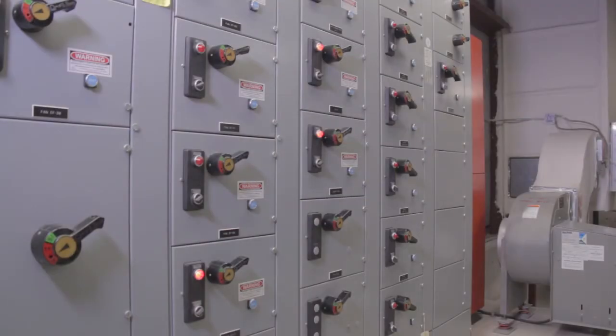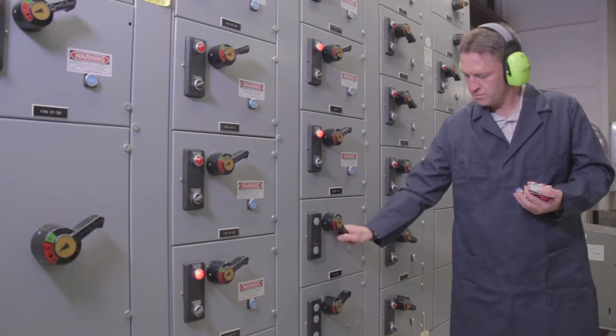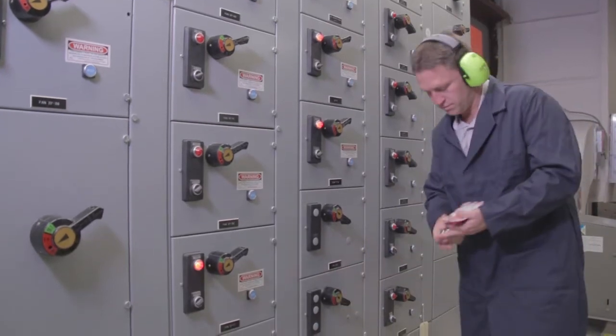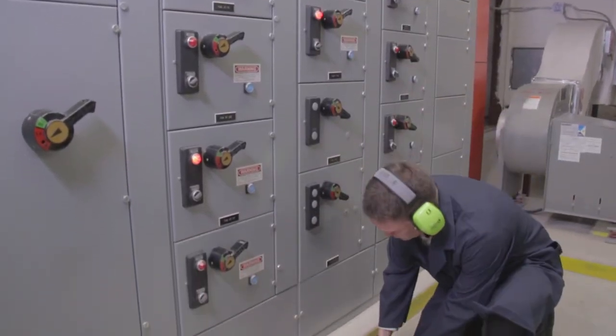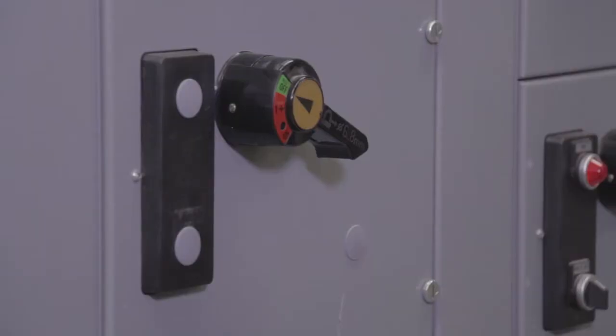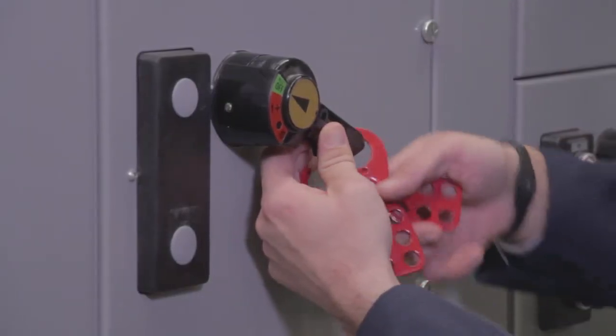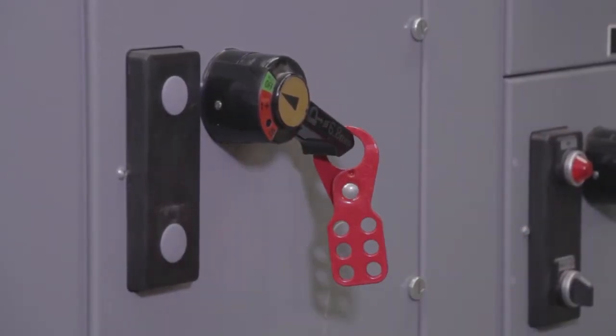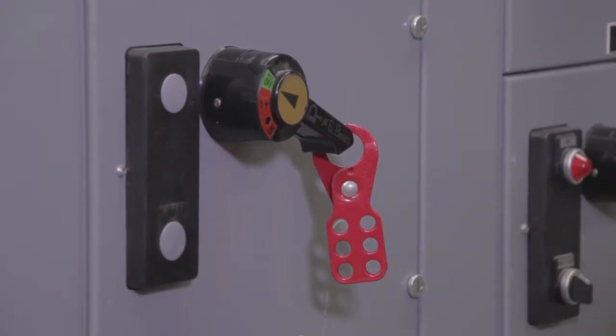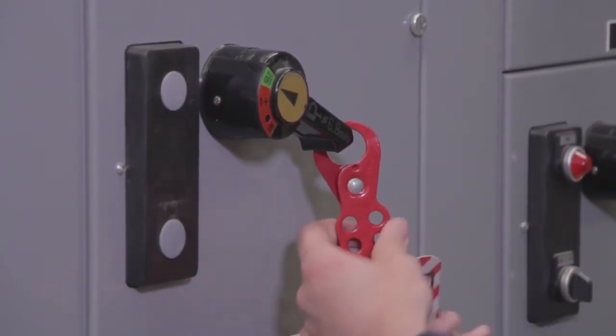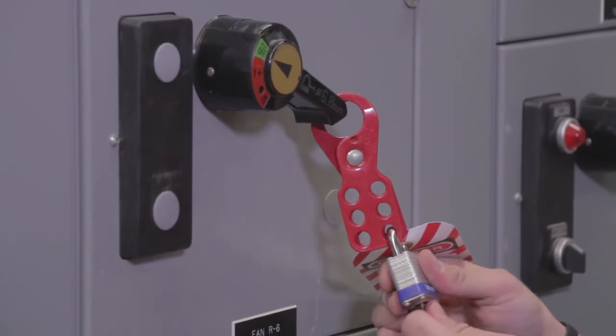Since we're completing a lockout/tagout on the air handling unit, we need to turn off the power source and lock out that piece of equipment with a lock, a multi-hasp, and a tag. The tag must be clearly visible and attached to the lockout device padlock and not the hasp. If the tag is not visible, you must add a second tag to an area where it can clearly be seen.